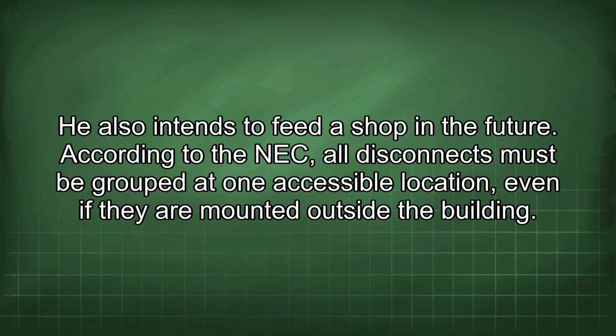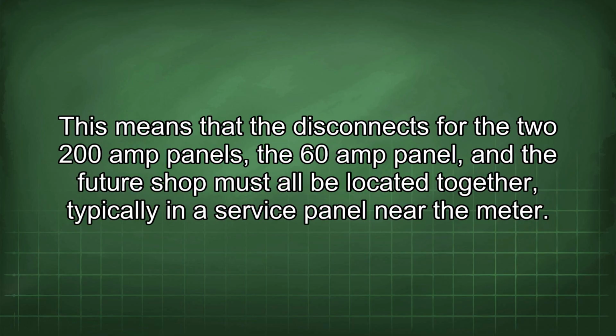According to the NEC, all disconnects must be grouped at one accessible location, even if they are mounted outside the building. This means that the disconnects for the two 200 amp panels, the 60 amp panel, and the future shop must all be located together, typically in a service panel near the meter.